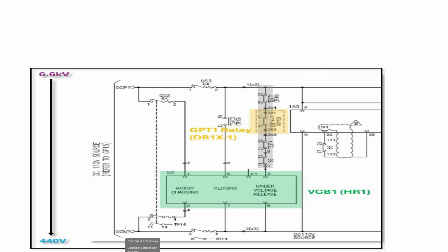The voltage is supposed to come in and go through this GPT-1 relay, which is a relay in the GPT-1 panel. This relay, as you can see, is labeled 381 right there - that's that block number they pointed out earlier. That's the one that failed, and it's wire number 1.